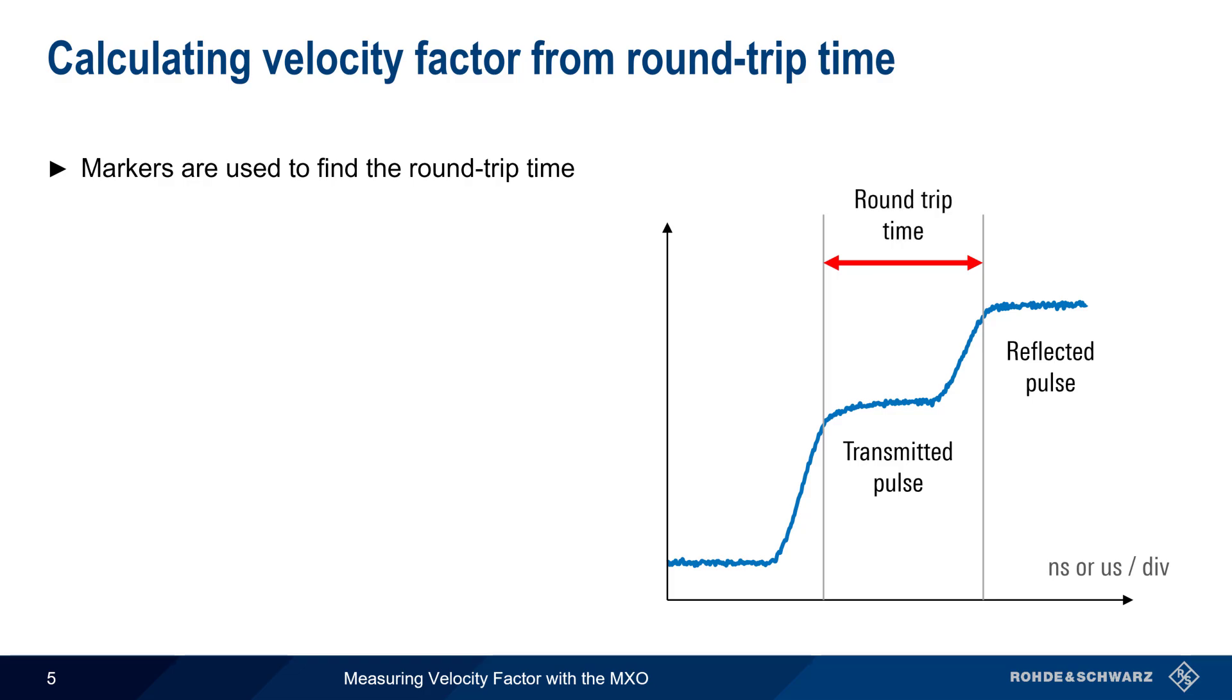Here we see an oscilloscope capture, showing both the transmitted pulse as well as the reflected pulse. Note that the scope's time base will need to be on the order of nanoseconds, or low microseconds, for most cable lengths. Markers are used to find the round trip time, and one-way time is simply half of this round trip time.